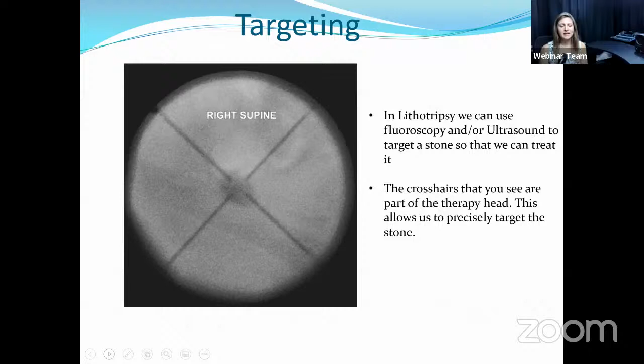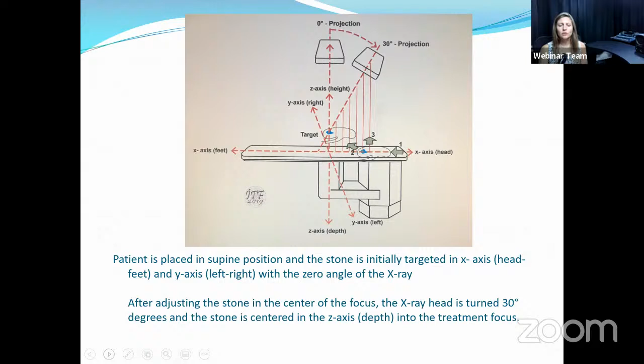This is an example of how the focusing of the shock wave reaches the stone, and it's a bit complex to explain, but eventually adjusting the stone in the center of the focus, and turning the X-ray head 30 degrees, can allow the stone to be at the center and the depth to be on the right level for the treatment to be focused on it.